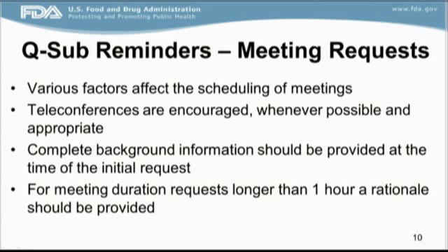Thirdly, in order to ensure that FDA staff have time to review and prepare for a meeting request, sponsors should provide complete background information that is targeted and focused at the time of their initial request. If new or modified background information is provided after the initial request, the meeting may have to be rescheduled. Additionally, FDA recommends meetings no more than 1 hour long. If a sponsor believes they need more time than 1 hour for a meeting, they should provide their rationale for the duration they propose in their request.